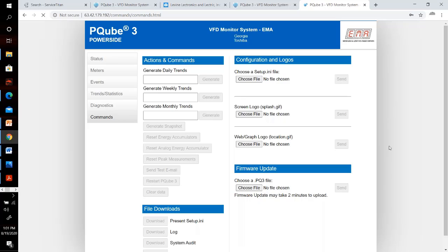So we can put in limits. If we go under commands, we can put in limits, tell it to generate reports. But there's one digital output where we can also tell it, if these conditions happen, I want you to shut down the drive. So from that perspective, it can control the drive, and at the same time we can send data back to us. We can talk to it with Modbus, Ethernet/IP, and BACnet. Those are the three protocols it understands.